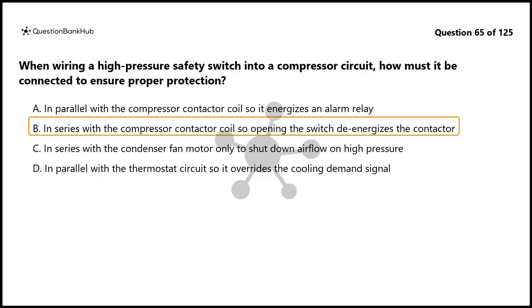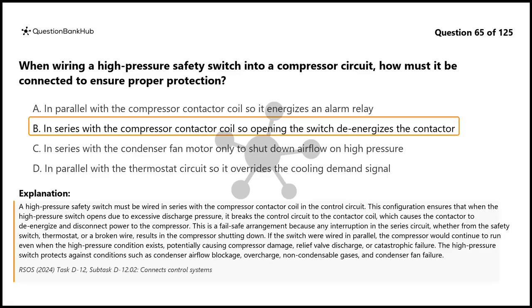The correct answer is B. A high-pressure safety switch must be wired in series with the compressor contactor coil in the control circuit. This configuration ensures that when the high-pressure switch opens due to excessive discharge pressure, it breaks the control circuit to the contactor coil, which causes the contactor to de-energize and disconnect power to the compressor.